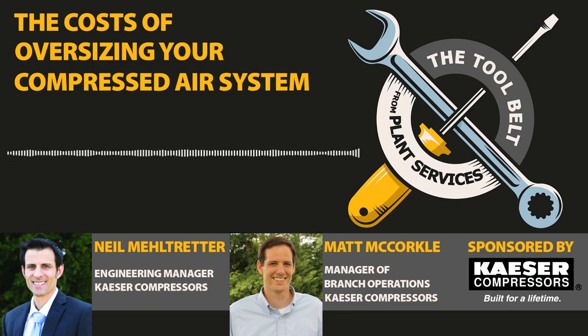So, if you're at 50% duty cycle, that's probably the worst place you could run a load-unload oil-flooded rotary screw compressor, which is typically what you'd see in a compressor room. If your duty cycle's, say, 70, 80%, that's probably in a better position. We like to size systems so that you're closer to 100%, 90% plus, and that really lends to splitting the load between multiple machines. And we'll talk about that a little bit later.